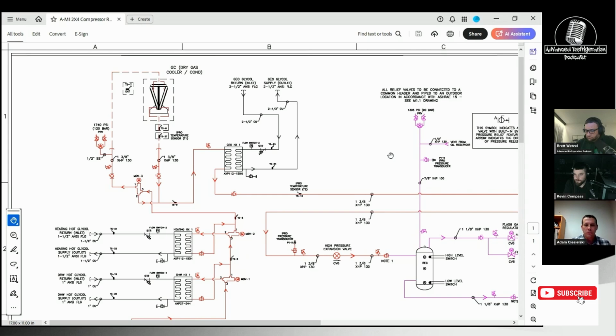But in a typical reverse cycle, you're dumping that back into the receiver. And if that receiver is running essentially 34 or 41 degrees, typical saturation temperatures, that is your defrost temperature. So essentially, when you defrost, you're really not condensing.